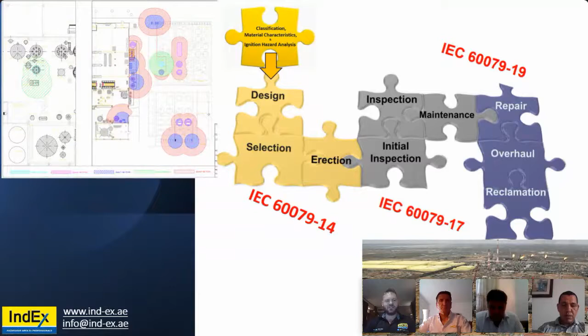When we talk about hazardous areas, there are many stakeholders involved. From the beginning, there's hazardous area classification, these zone drawings. There are multiple standards that define this: 60079-10 for classification, -20 for the material characteristics. Then there are multiple for ignition hazard analysis.